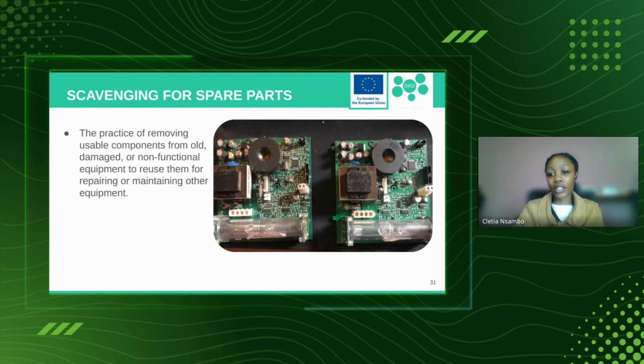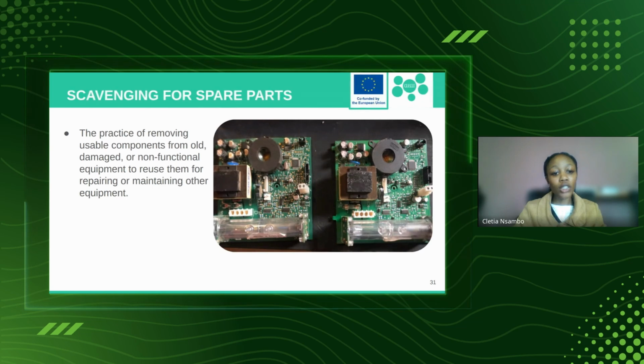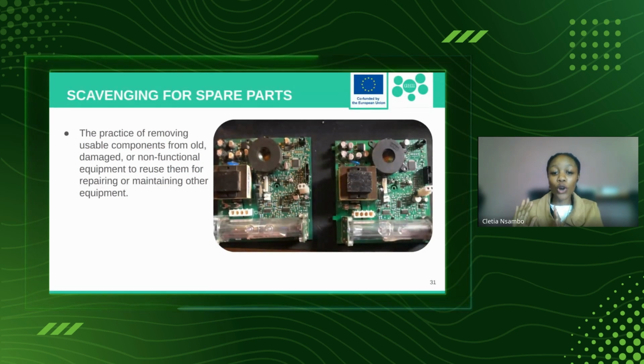For example, at a facility, if you have an old concentrator, you can take parts of it that can still be used. In the picture on this slide, these are two boards from an oxygen concentrator, just as an example. If the oxygen sensor on one is broken, but you have an old, unfixable oxygen concentrator with a functional oxygen sensor or board, you can take that functional part and replace it in the one you're fixing.